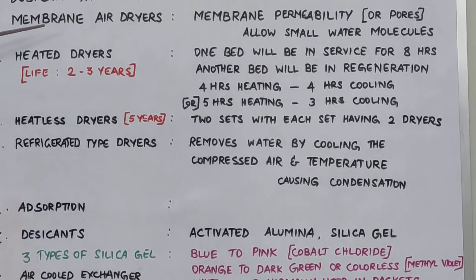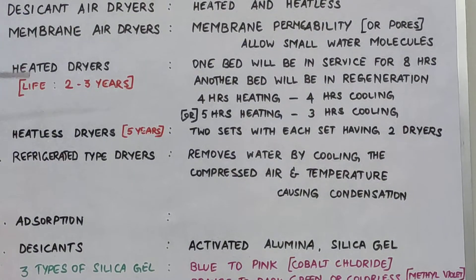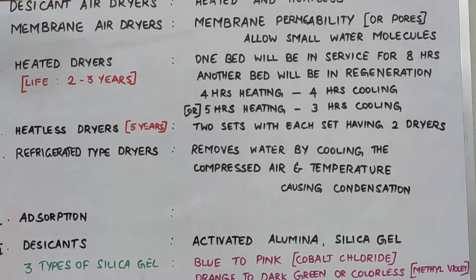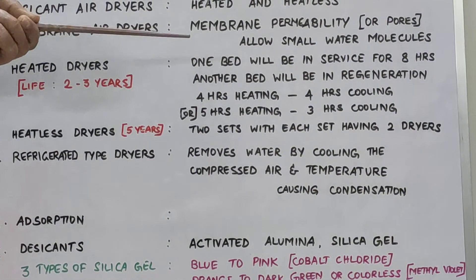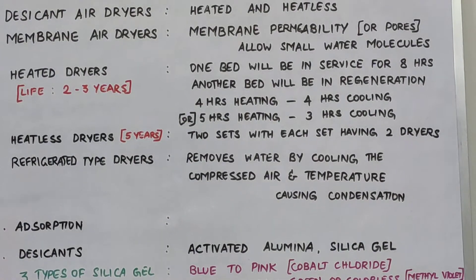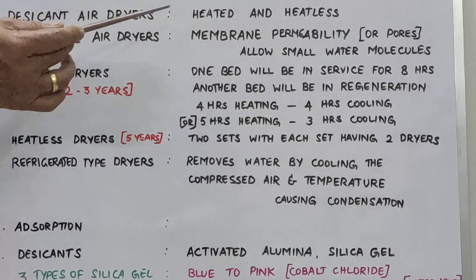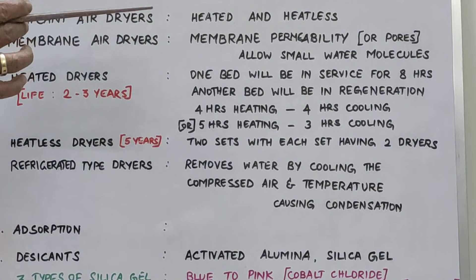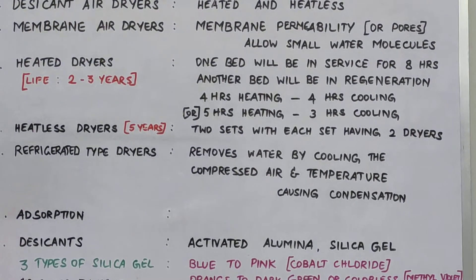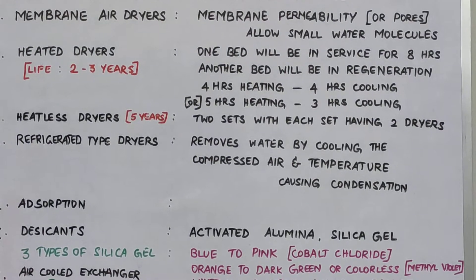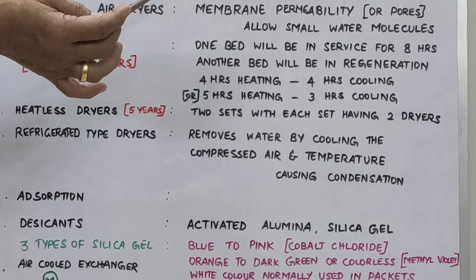Another type of dryer is the membrane type, which is commonly used in offshore and marine applications. The membrane uses permeability to allow small water vapor particles to pass through the membrane wall, while larger molecules of nitrogen and oxygen do not pass through and exit the unit as dry air. The membrane is a hollow membrane tube, and the water particles collected outside the tube in the chamber are purged using recirculated dry air.